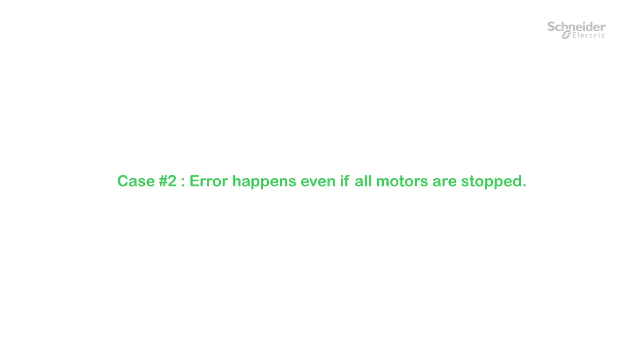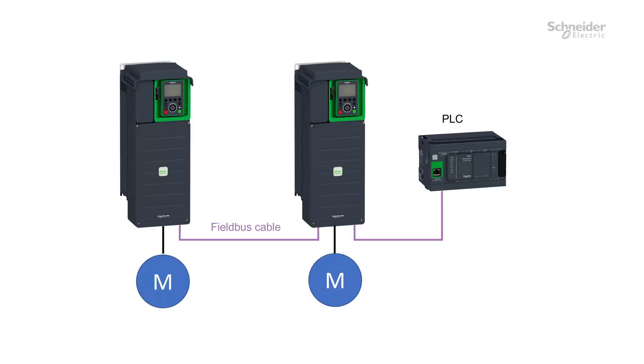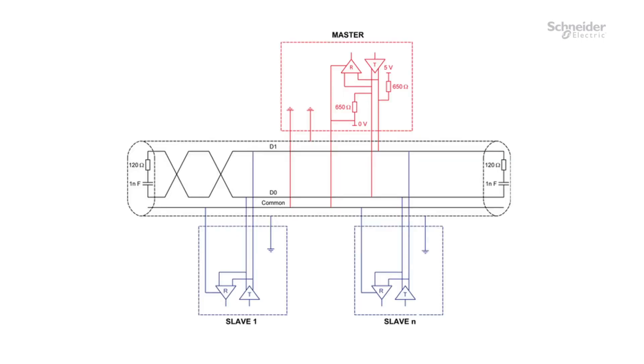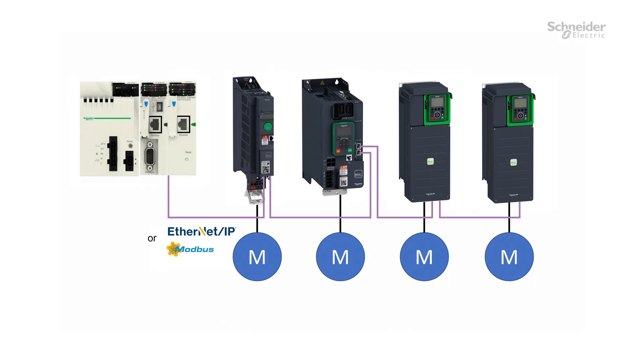Case number two: the error happens even if all motors are stopped. If the communication error is triggered even when your application is not running, follow these instructions. The first point to check is the line resistor for CANOPEN, PROFIBUS, Serial MODBUS, or BACnet. The second point is to check the timeout settings. If you are using Ethernet or Serial MODBUS, this timeout can be adjusted on the product side using the Graphic Display Terminal or SoMove.